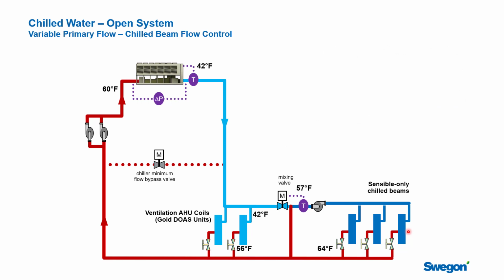So let's talk a little bit about the control. The chiller plant would be set up through the chiller controls to deliver the water temperature for the lowest temperature you need. That's going to be the air handling units, right? So we're showing 42 degrees here. Could be 44, could be 40, whatever the design requirements. And that water is used to do the dehumidification in the air handling units. So you can see the primary air handling units are getting 42 degrees.